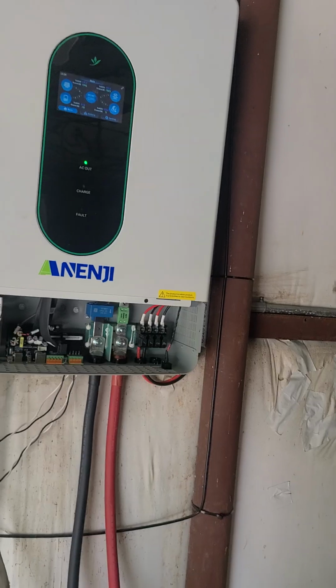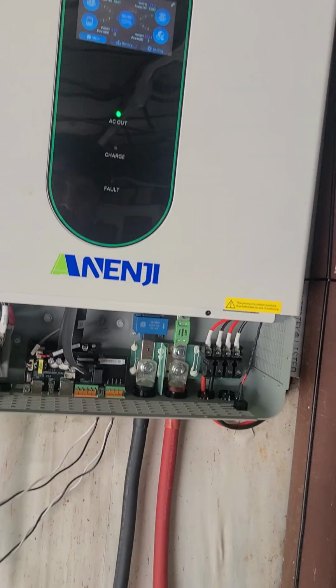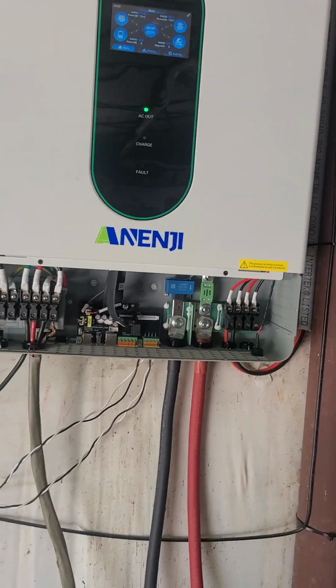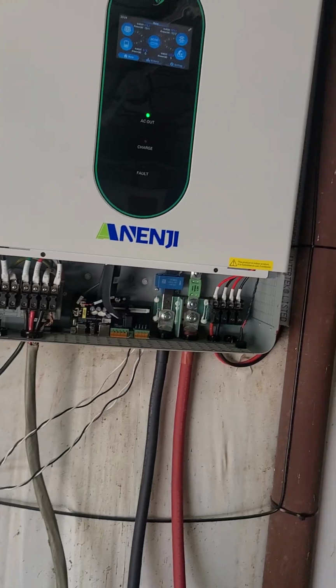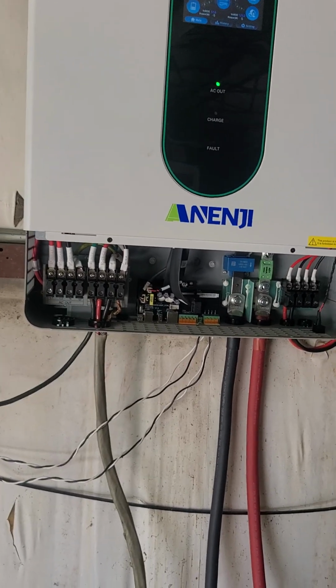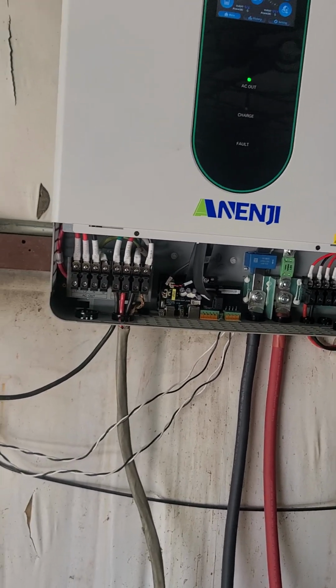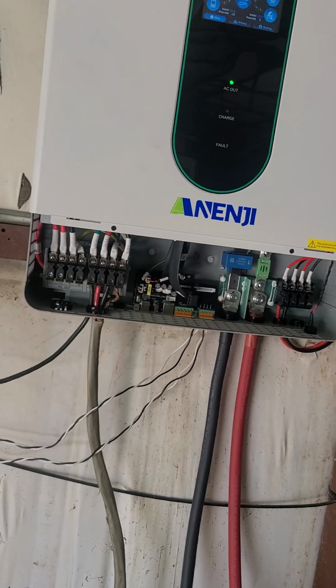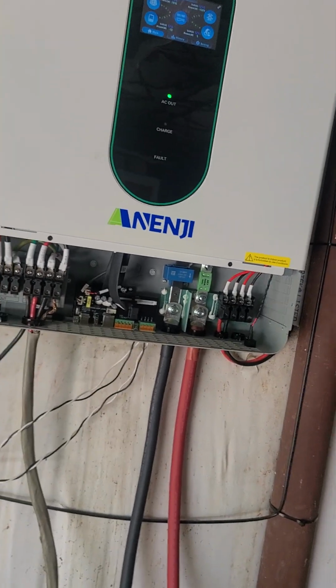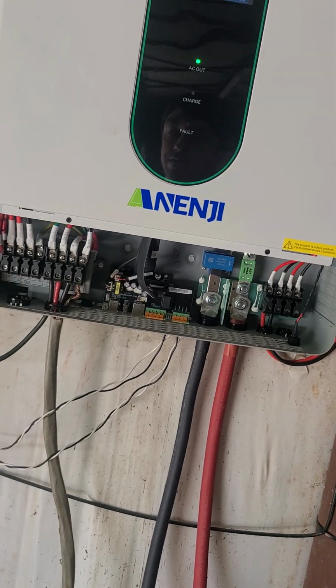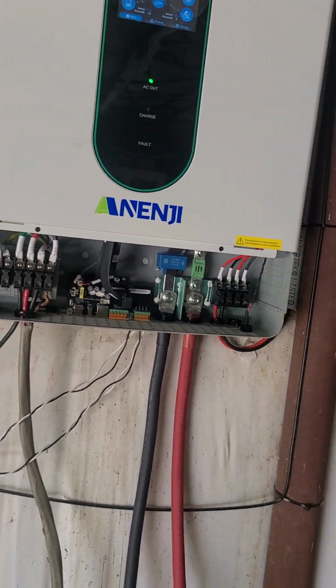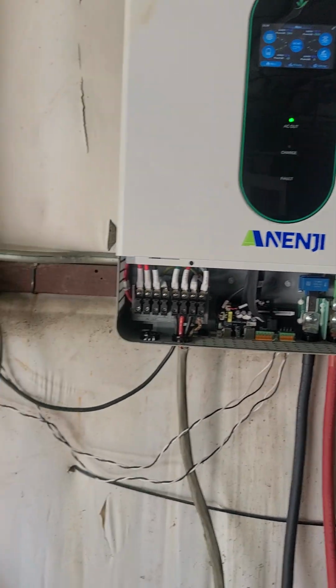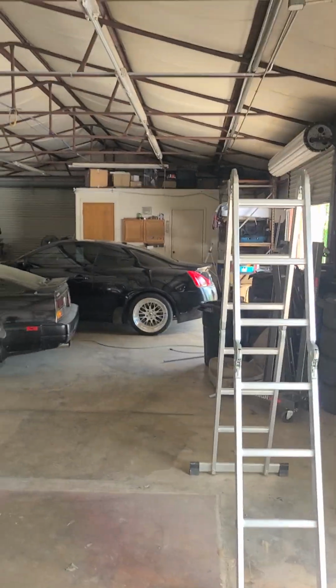In pass-through mode, we'd be able to pass through if we had battery power and solar power coming in, and use a total of 24,000 watts for the house. But if our batteries were dead and it were nighttime with only grid to pass through, we could only pass through 12,000 watts. So we'd just have to not be stupid—don't run everything at once.